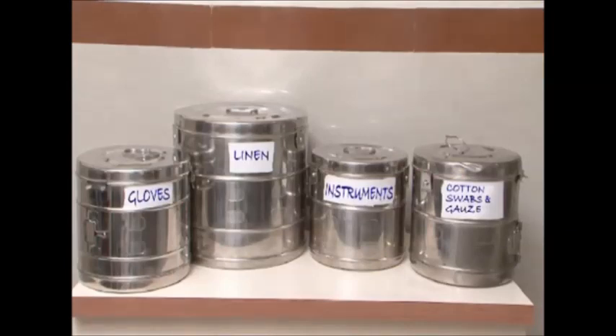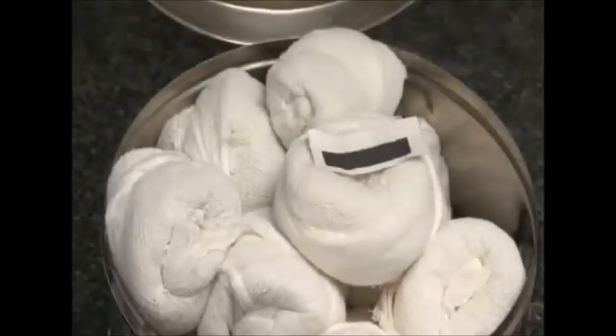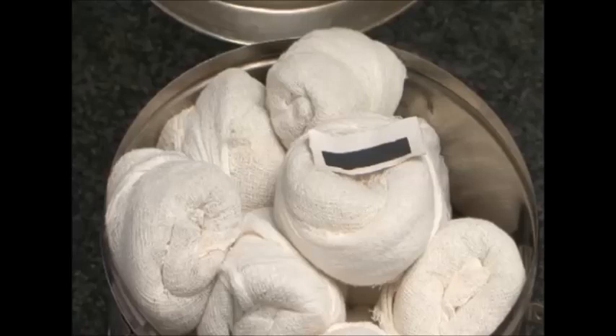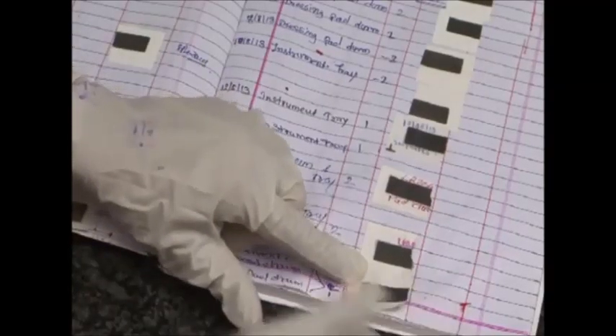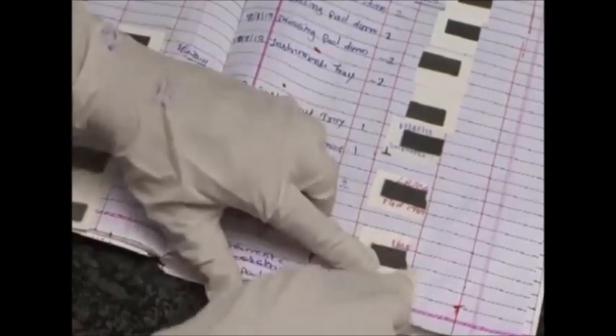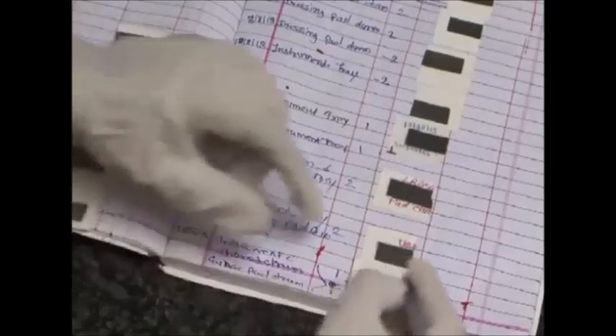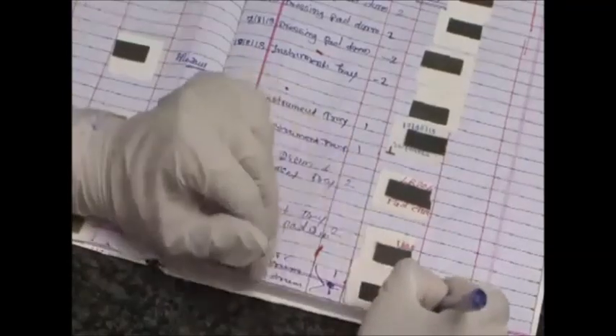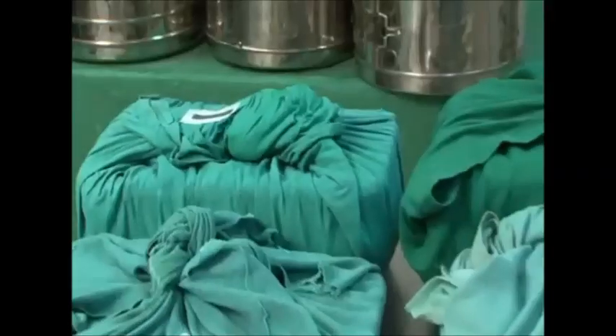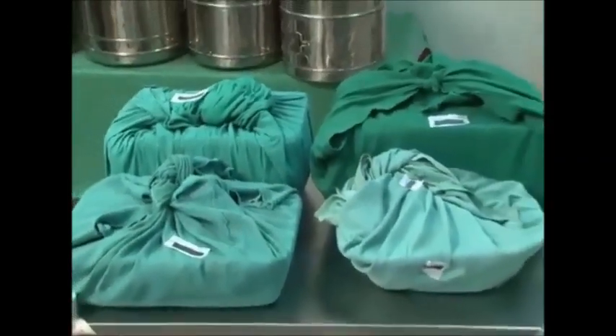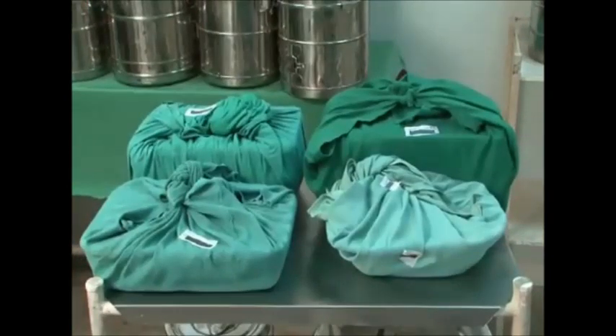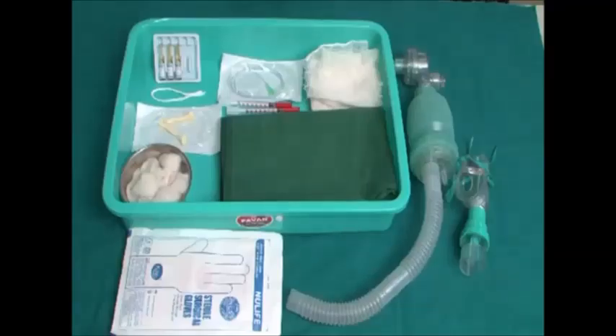Drums containing sterilized items like gloves, linen, instruments, cotton swabs and gauze pieces. When you open the autoclave drum, confirm that the color of the strip inside the drum and on the wrapped sets has changed. Remove the strip and place it in the register. If there is no color change, the items have not been properly sterilized and the drum needs to be sent for autoclaving again. Each delivery tray should have pre-autoclaved and wrapped instruments in enough numbers so that one set is available for each delivery.